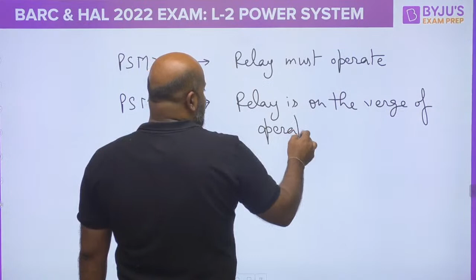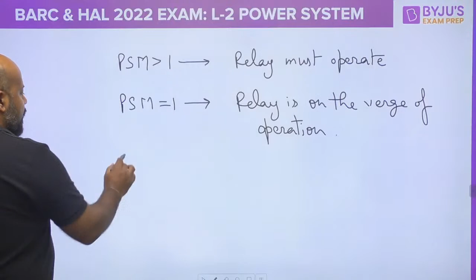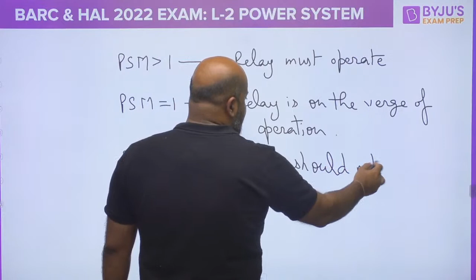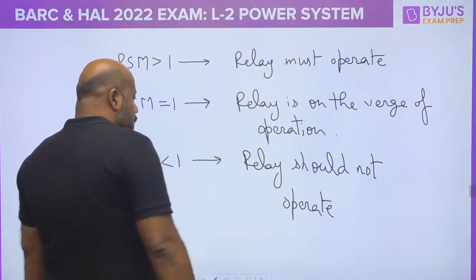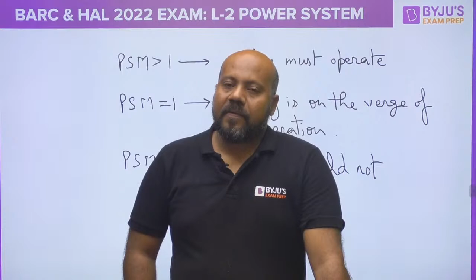Now listen very carefully. As I told you, the plug setting multiplier gives you very important information about the severity of the fault. Now understand, this plug setting multiplier can give you some more information. If the plug setting multiplier is more than 1, what does it mean? It means the relay must operate. When the plug setting multiplier is equal to 1, it means the relay is on the verge of operation. Verge of operation means about to operate, not yet operated, but about to operate. What happens when the plug setting multiplier is less than 1? It means the relay should not operate. Is it clear, everybody?